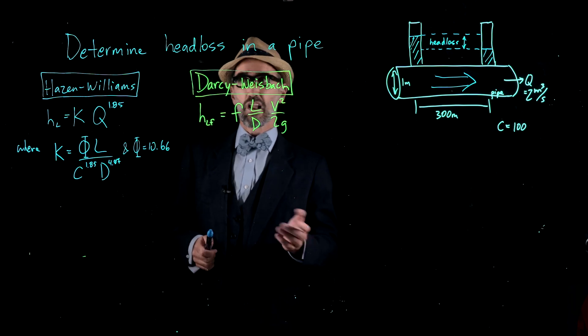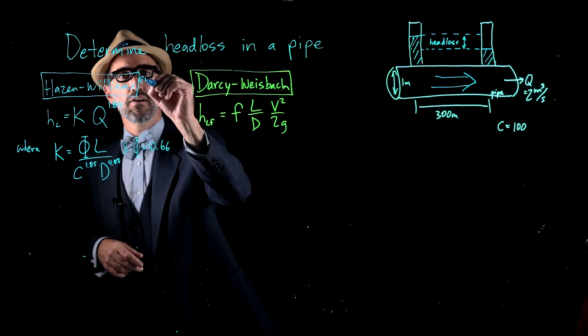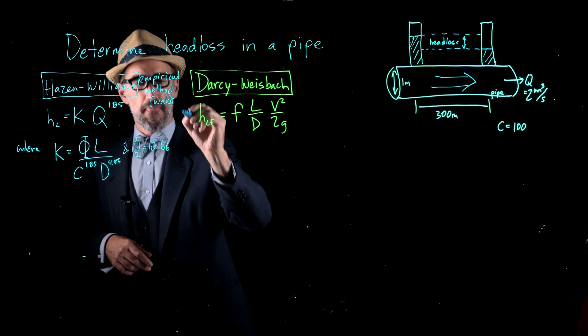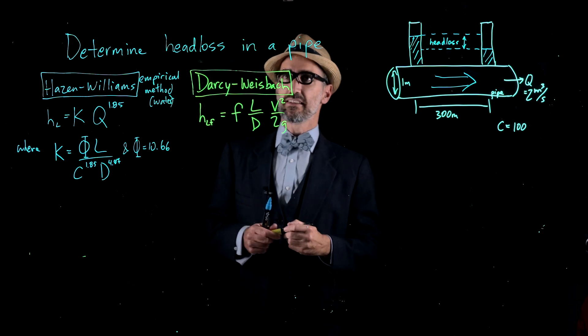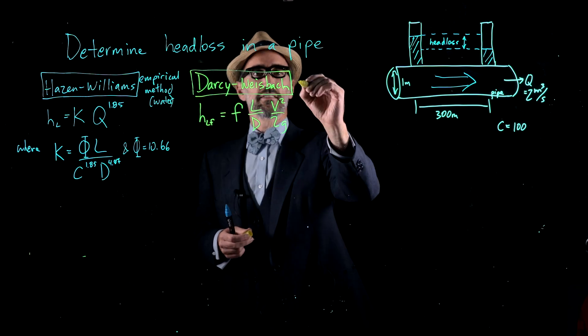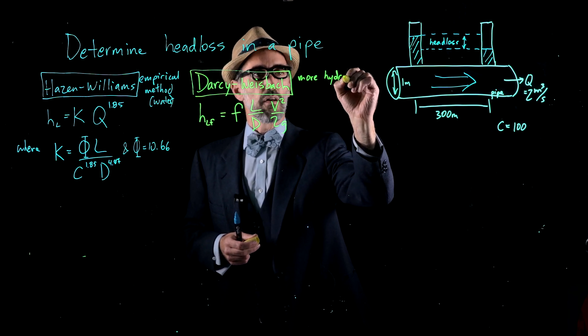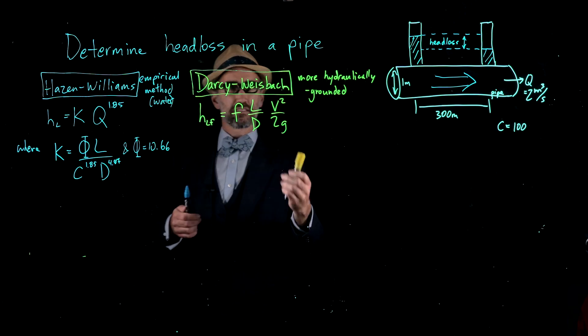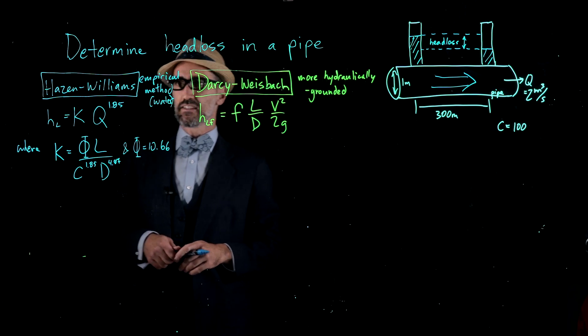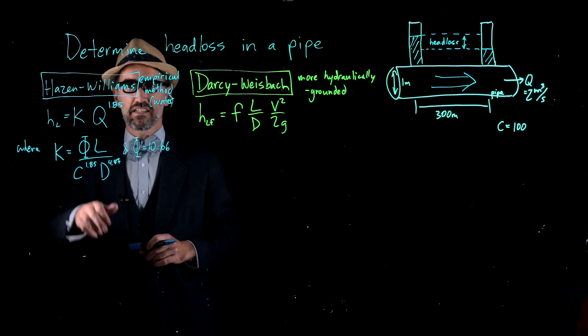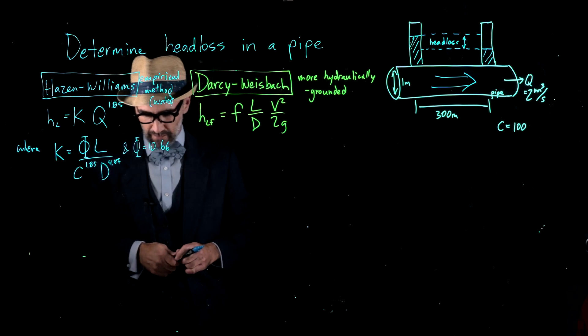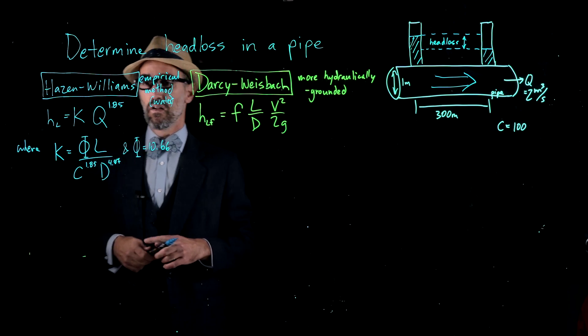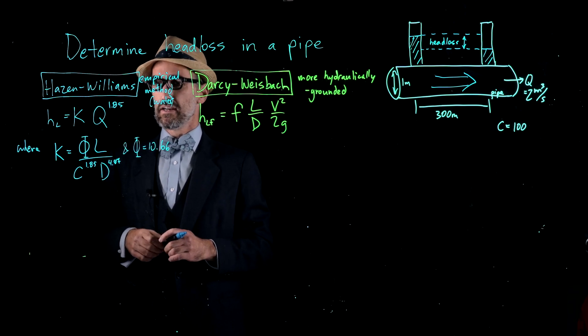First, we'll solve for head loss using the Hazen-Williams method, which is a more empirical method and is only for water — important to remember. Second, we'll calculate head loss using the Darcy-Weisbach method, which is more hydraulically grounded. We'll use the Moody diagram and Reynolds number in the Darcy-Weisbach equation. Using the Hazen-Williams equation: HL equals K multiplied by Q to the exponent 1.85, where K equals phi multiplied by L, all over C to the 1.85 multiplied by D to the 4.87.